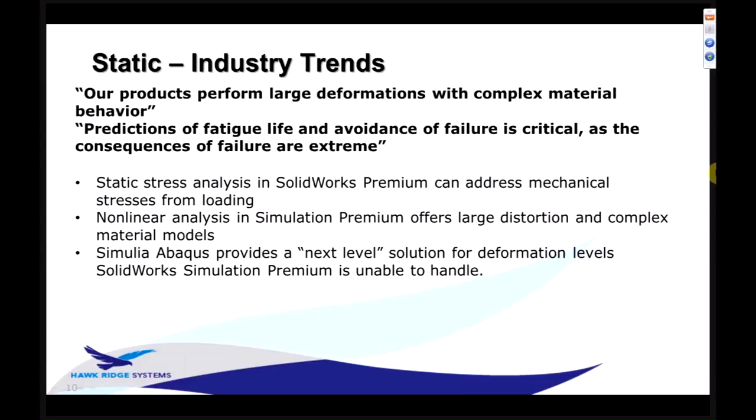And the other thing is predictions of fatigue life become important. Right? If you're putting an object, especially implantable stuff, you've got to be absolutely sure you're not going to see a failure during the expected lifetime of that product, because the consequences can be devastating, both financially in terms of returns and litigation, and also for the patient involved.